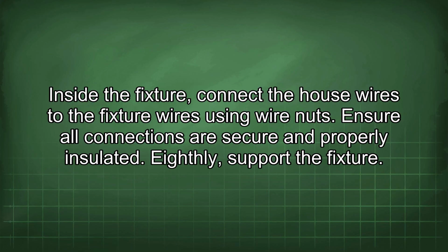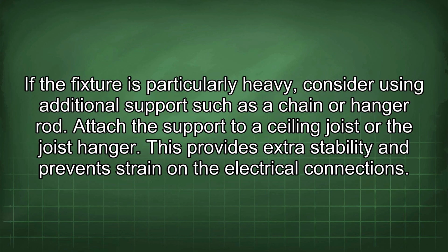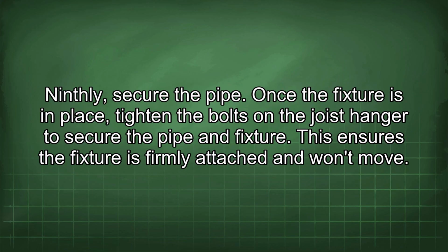Eighthly, support the fixture. If the fixture is particularly heavy, consider using additional support such as a chain or hanger rod. Attach the support to a ceiling joist or the joist hanger. This provides extra stability and prevents strain on the electrical connections. Ninthly, secure the pipe. Once the fixture is in place, tighten the bolts on the joist hanger to secure the pipe and fixture. This ensures the fixture is firmly attached and won't move.